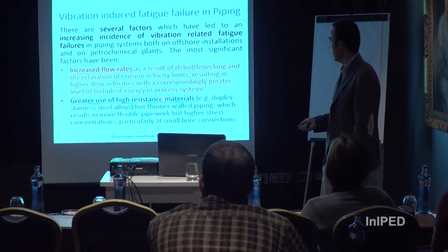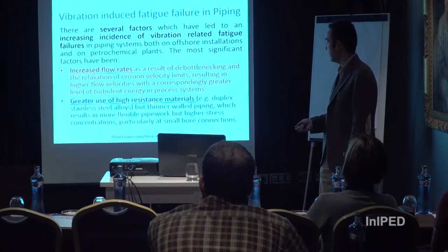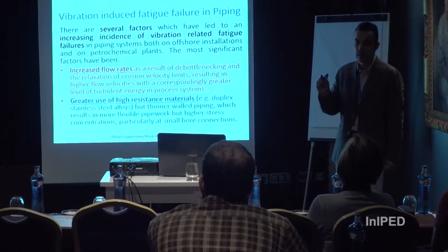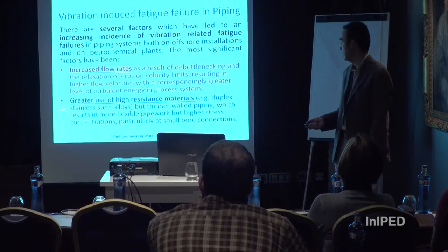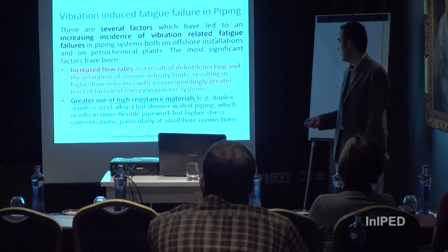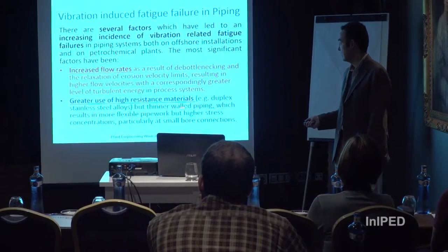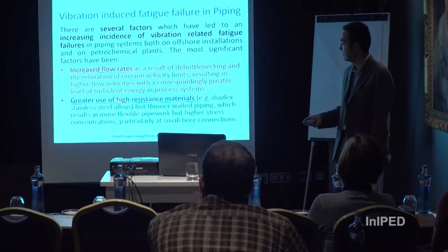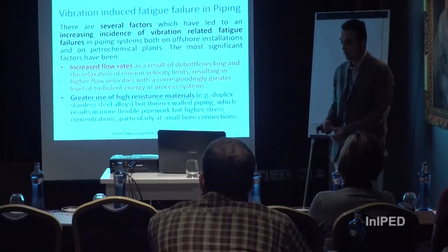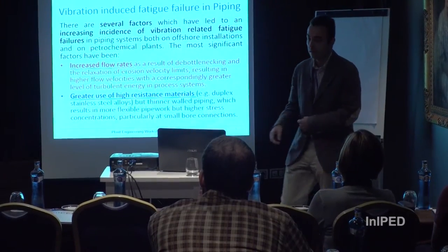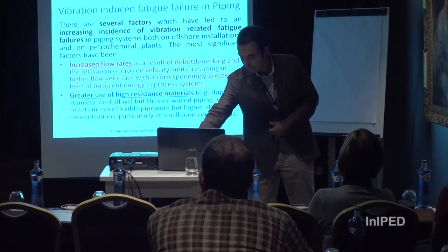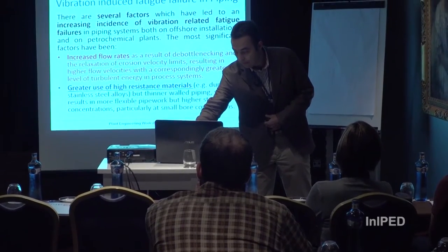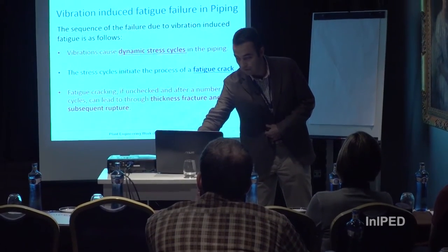Another contributing factor has been the use of high-resistant materials. When we use high-resistant materials, we use thinner wall pipe. It is more flexible, but it is more subject to these mechanisms and more sensitive to this type of fatigue failure due to vibration.